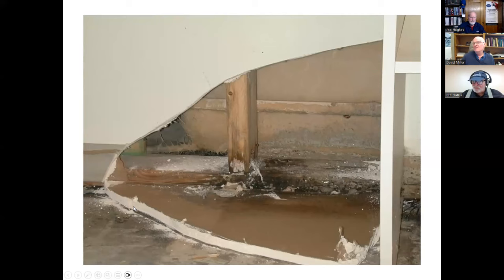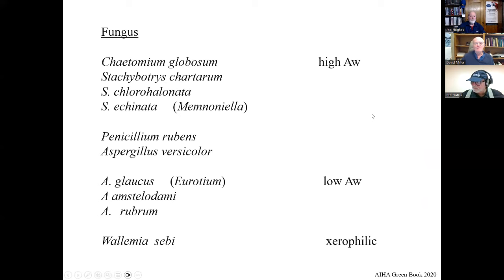And I use this to make the point that to get wood to grow fungi or especially molds, to raise it to the level of moisture where it'll support actual growth on wood, it's about 15% by weight. But to get that for paper face gypsum wallboard, it's about 0.5% by weight. So I know people have that intuition. But it also allows us to think about the scientific term I know I've used before in some of our discussions, and that's water activity. So I will raise a little bit about how that can be useful.